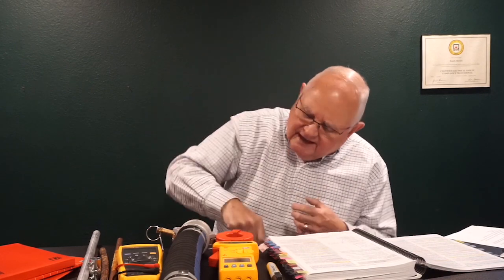So why would we ground? Why would we take a perfectly good electrical distribution system, I'm talking about going to the windings in the transformer, the generator, and take those windings that are producing electricity and connect a wire to those windings and take that wire and connect it to the earth? That doesn't sound too smart. In fact, over 100 years or close to 100 years ago now, they had even taken the concept of grounding out of the code for a while, I understand. But anyway, a long time ago.